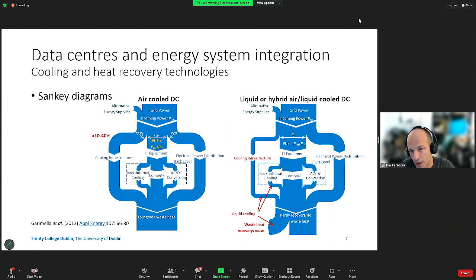So with the use of liquid cooling, what we can do is slightly change the balance here. And then there are a few things that will happen. The PUE value will typically drop, which is a good thing. The cooling infrastructure will take up less energy, but primarily you will now be able to partly, never completely probably, but partly recover some of the waste heat and reuse that in a different part of the energy system.